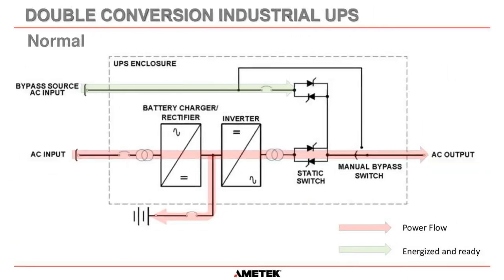So we'll give you a reminder of how a UPS works and the power flow of the system in the different modes of operation. You can see on the screen here, the red is the power flow and green is energized and ready to supply power if called upon. So we have our 3-phase AC input on the left-hand side here, usually a 480 volt supply from your MCC. That goes in, this input breaker is on our UPS, and this input transformer is inside the UPS. This dotted line on the outside here shows you what is actually inside the UPS itself.